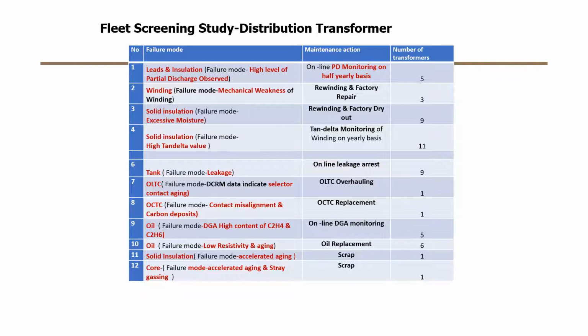So for lead and insulation failure: high level of discharge observed on the lead. What is the maintenance action? PD monitoring on a half-yearly basis. Suppose it's an unknown domain and we have not done any PD monitoring - then we don't know there is a discharge.